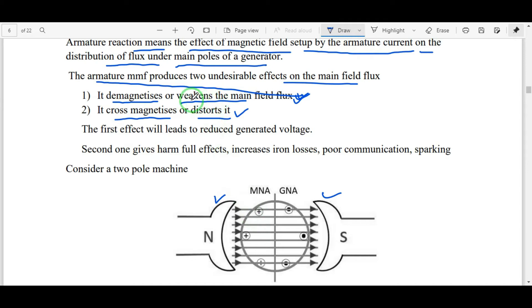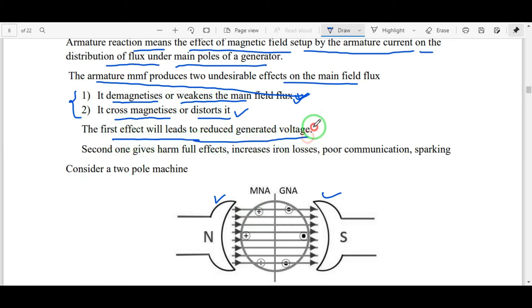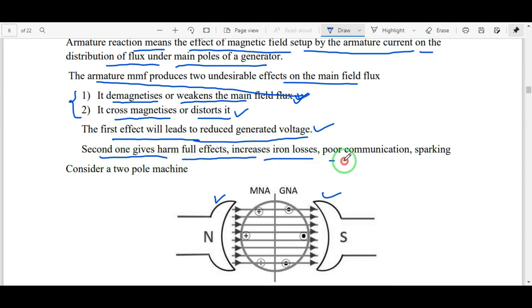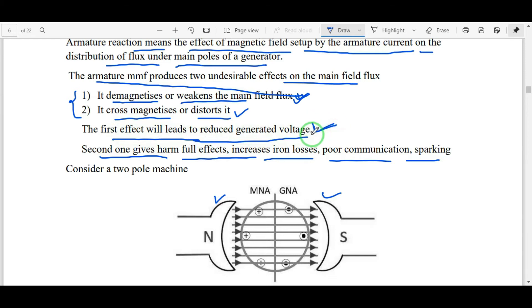The first effect — de-magnetizing — leads to a reduction in generator voltage. The second effect — cross-magnetizing — increases iron losses, causes poor commutation, and produces sparking.